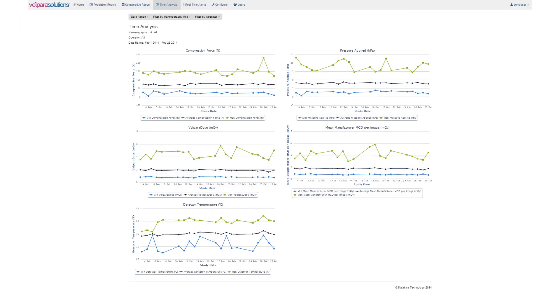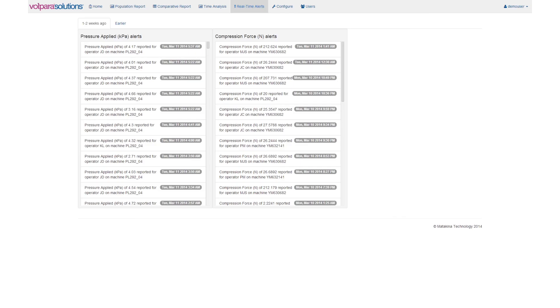Data can also be displayed over time to better visualise trends and maximum values. The time analysis displays variables by X-ray units and operators, which can be filtered. Some of the maximum values could be an area to investigate. Users can configure alerts for when dose, force, and pressure thresholds are exceeded, and these are listed in date order on this tab. Alerts can also be emailed to recipients.